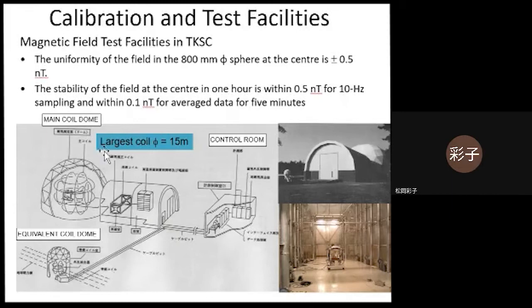We need a big coil system to have a uniform zero field area. In the case of the Tsukuba facility, the uniformity of the field is about an 80 centimeter diameter sphere, and inside this sphere, the magnetic field uniformity is within 0.5 nanotesla.